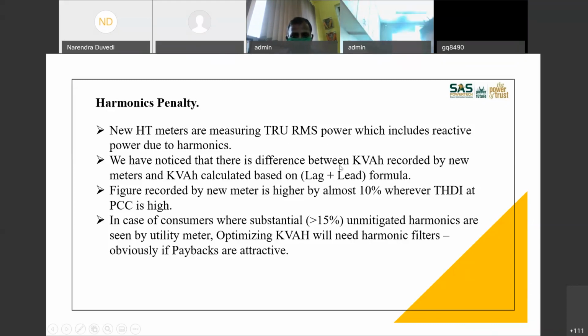We have noticed that there is a difference between kVAh recorded by the new meters and kVAh calculated based on the lag plus lead formula. Even if you see your bill from April, you will see that the power factor calculated is still based on the lag plus lead formula, which is available in the bill. But if you divide your kWh by kVAh, which are mentioned in your bill, that will differ from this power factor formula. There is about a 10% difference. The meter will record 10% more kVAh if your harmonic distortion is more at the meter end. Wherever there are MSEDCL meters, if your HT side harmonic distortion is more, typically say 15% or more, you will get a 10% difference, and that will prompt you that for optimizing kVAh billing, you will have to do some harmonic mitigation. Of course, if payback permits.